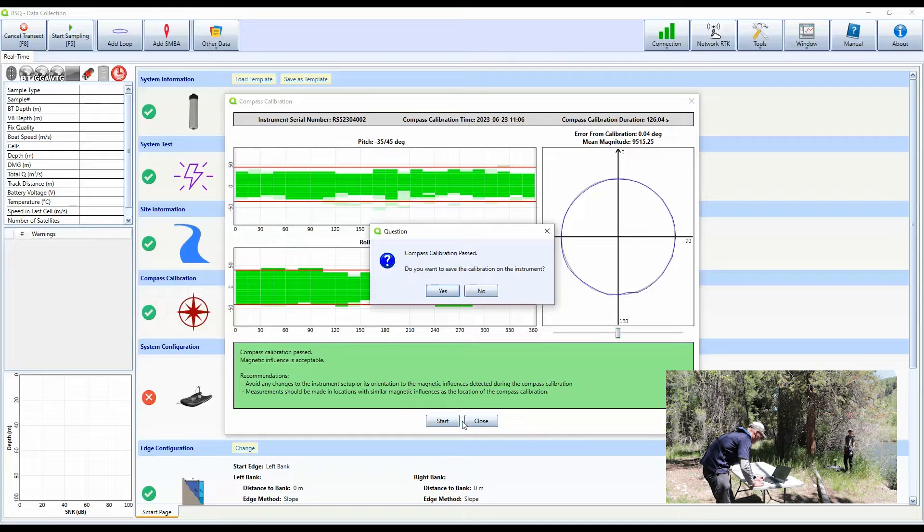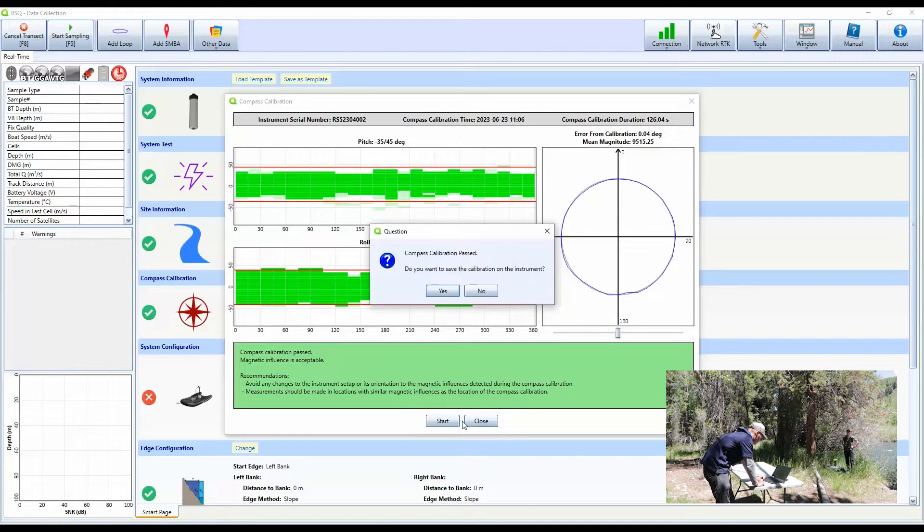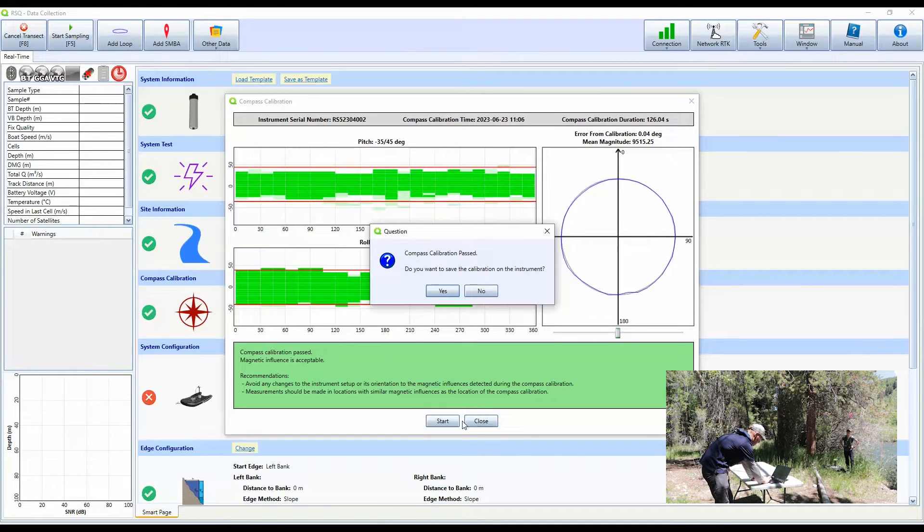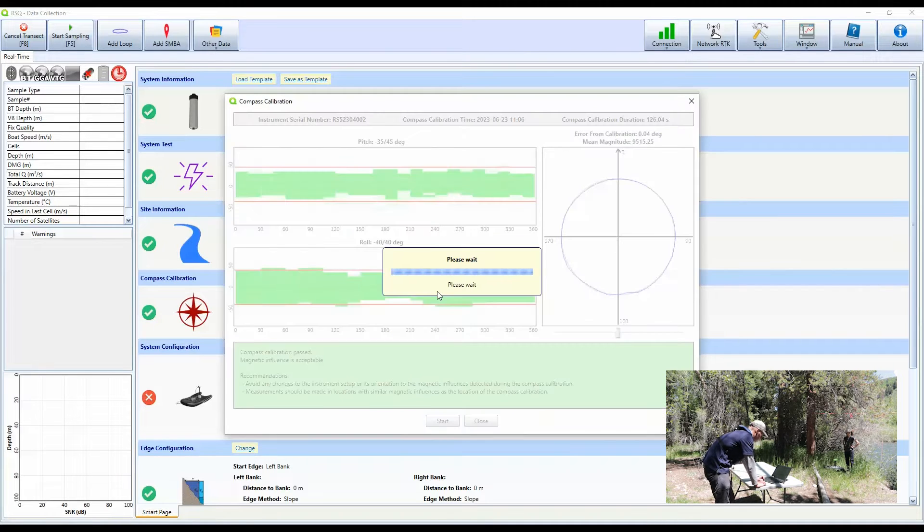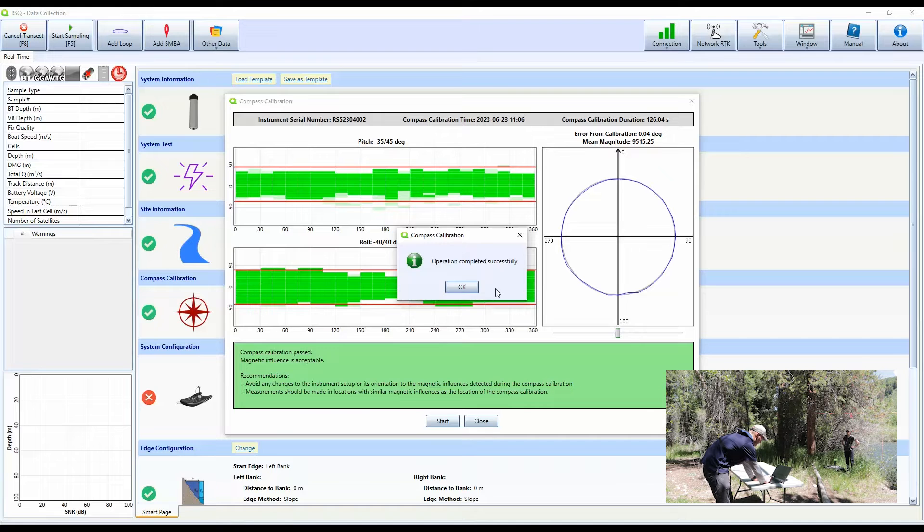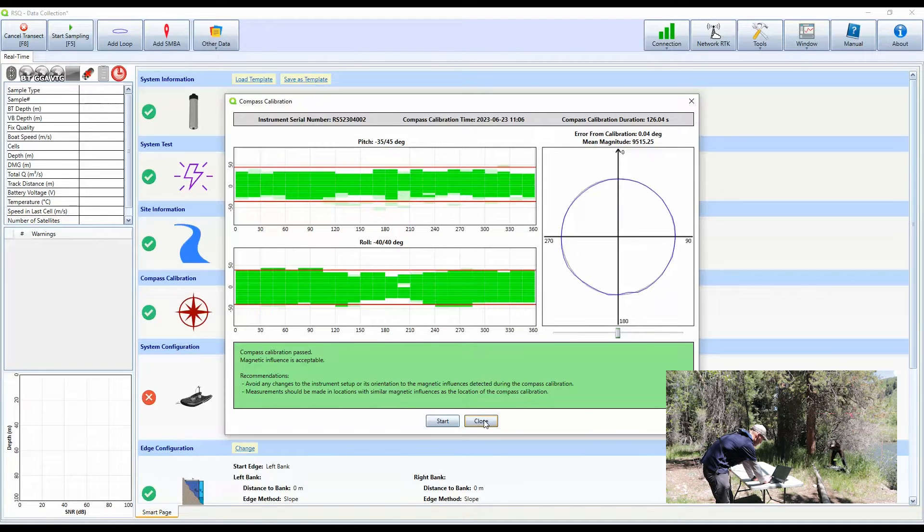And then now I get feedback. Compass calibration passed. Do you want to save the calibration on the instrument? Yes, it passed. I'm not going to say no and repeat. So now we have calibrated our compass and we can close this window.